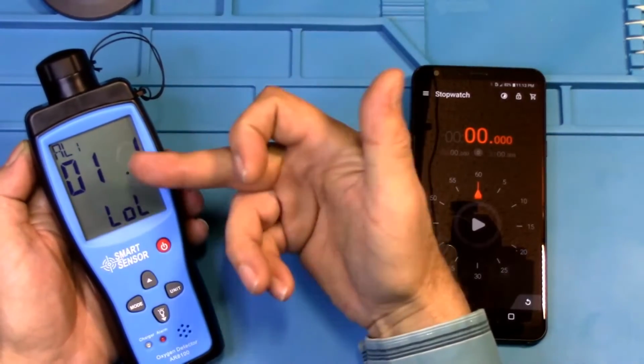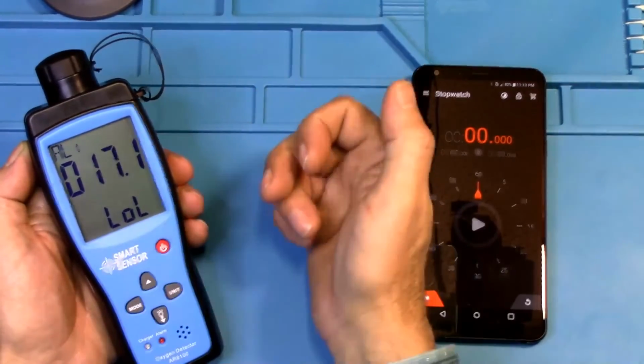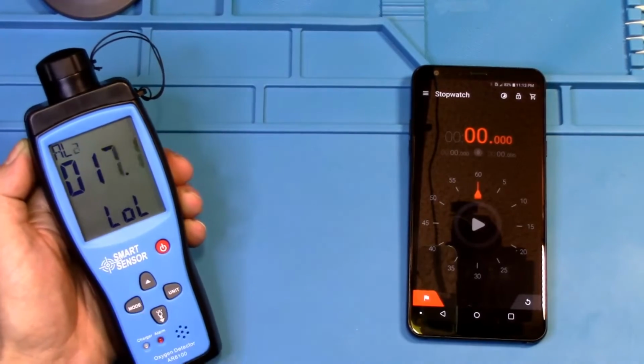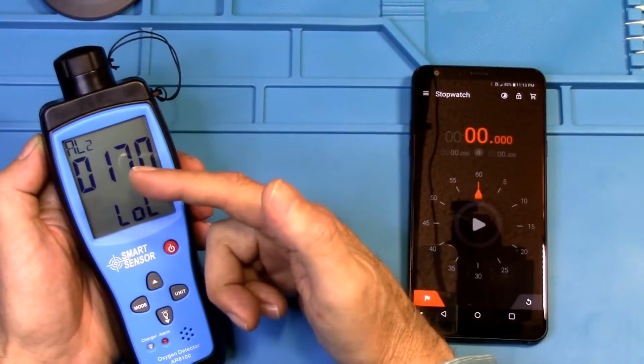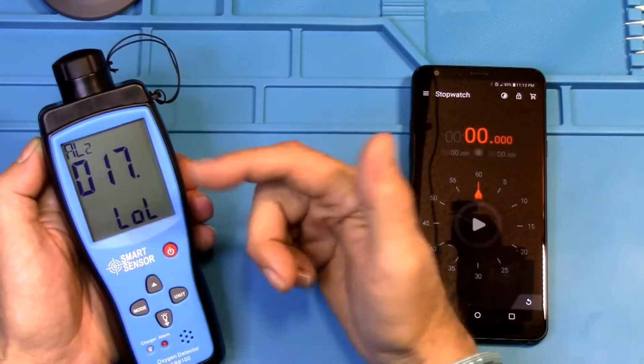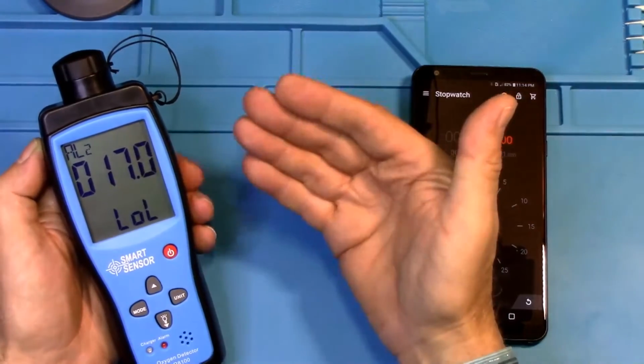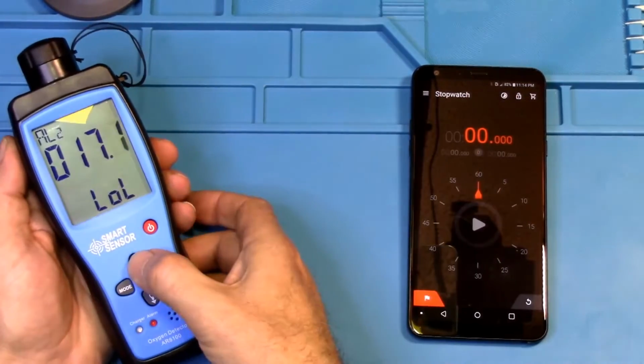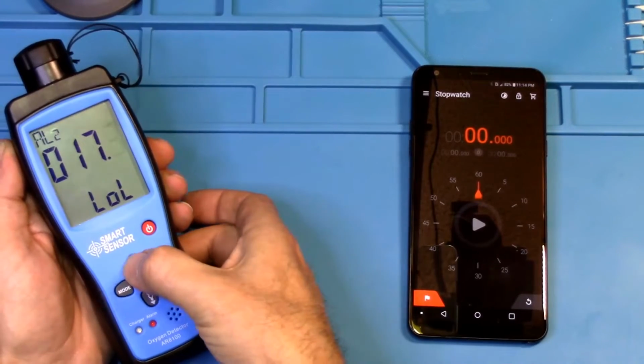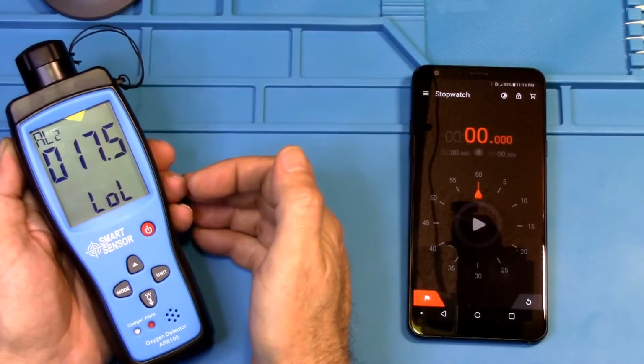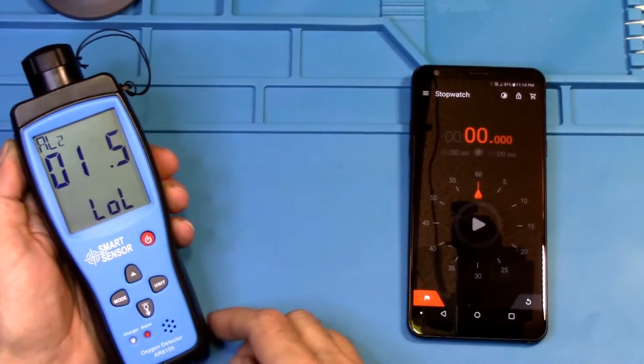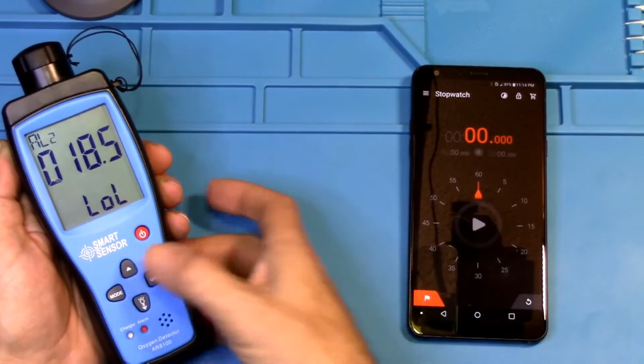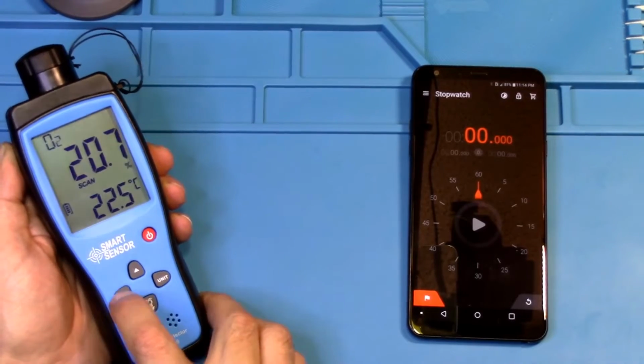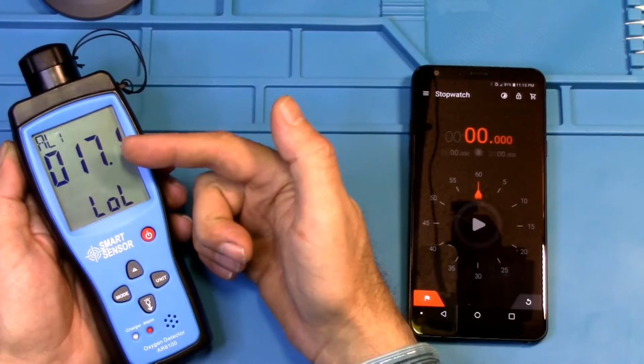Now that means anything below 17.1 is going to cause the alarm to go off. And then hit mode, and that will take you to alarm 2. I thought one of these was going to be a low setting and one was going to be a high setting, which actually there really should be a high setting. At alarm 2, we can press the up button to bring this decimal point up. We can hit the unit to go back to the 7, and then press that one to go up, and now it'll alarm at 17.5, and then press the mode button to accept it, and now the alarm is set for alarm 1 at 17.1 and alarm 2 at 17.5.